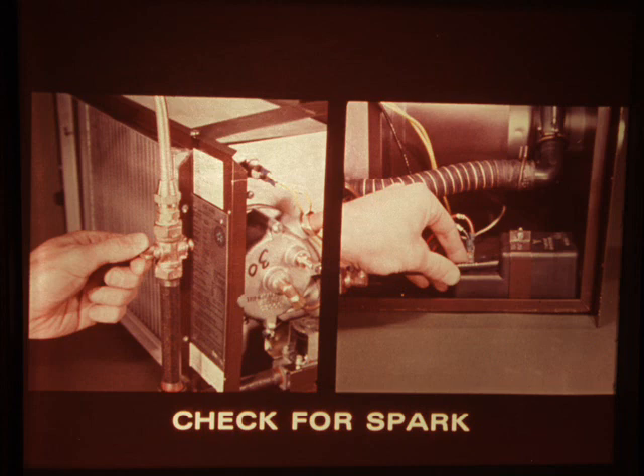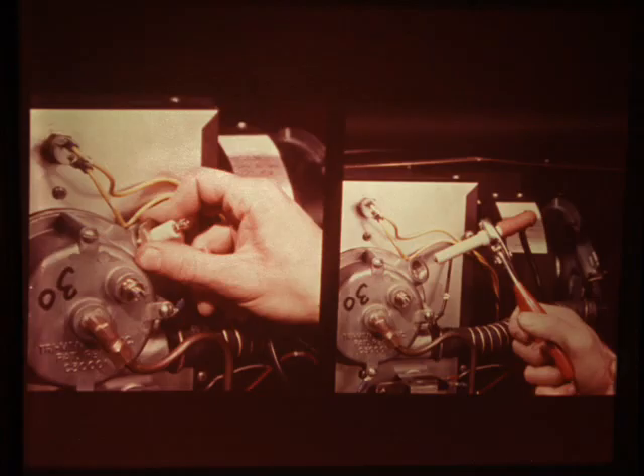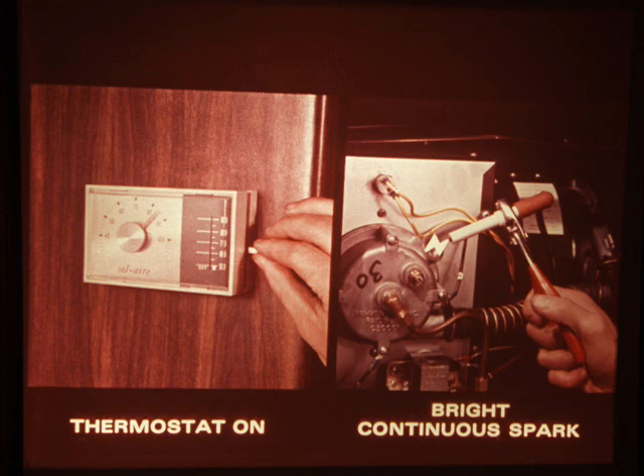First, check the furnace for spark. Turn off the manual gas valve on the furnace for safety during the check. Be sure the ignition high-tension wire is connected securely in the ignition pack. Remove the locking nut from the igniter and pull the igniter out of the burner. Using insulated pliers, hold the igniter about 1/2 inch from the burner. Then turn on the thermostat. There should be a bright, continuous spark at the igniter tip. If there is, the spark system is okay, and you next check for gas flow through the furnace. A little later, we'll tell you what to do if there is no spark.